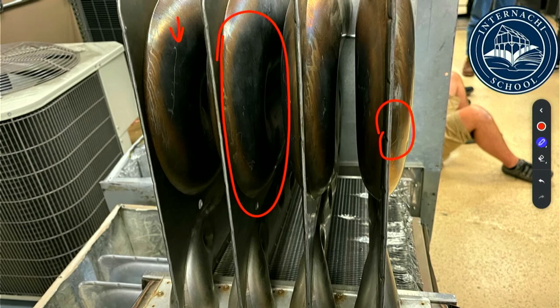What types of conditions typically cause heat impingement? Too high of gas pressure coming in, so it's too big of a flame coming across, or maybe it got bumped and twisted and it's blowing the heat on one side or the other. That's also going to happen if the flame is actually impinging and touching the heat exchanger, which disrupts the flame, and that's when you get those high levels of carbon monoxide.